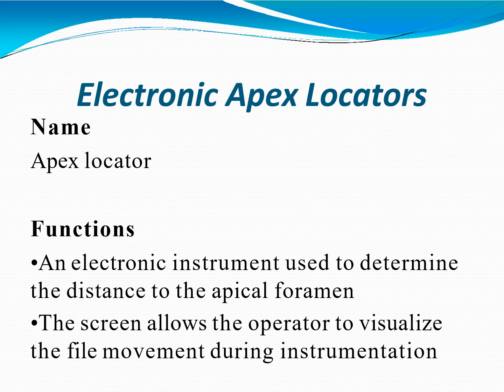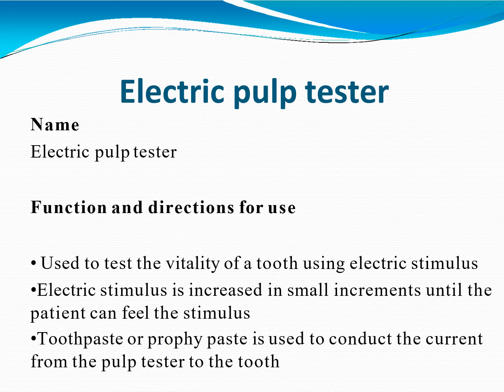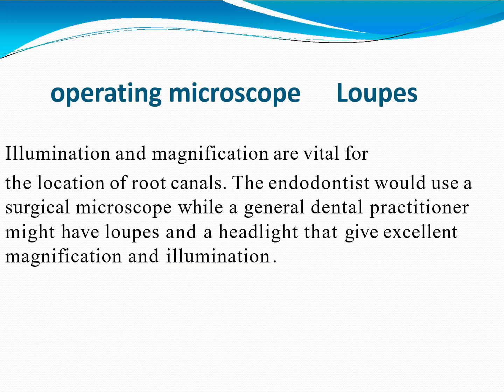The apex locator is an electronic instrument used to determine the distance to the apical foramen; the screen allows the operator to visualize file movement during instrumentation. The electric pulp tester is used to test the vitality of a tooth using electric stimulus, which is increased in small increments until the patient feels it; toothpaste or prophy paste is used to conduct the current from the tester to the tooth. Loupes and an operating microscope provide illumination and magnification vital for locating root canals; an endodontist would use a surgical microscope while a general dental practitioner might use loupes with a headlight.